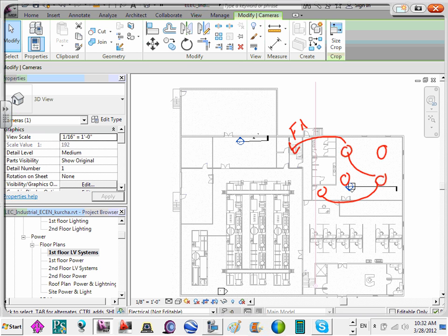that's going to your control panel. It's going to be circuit number 1. And then these two are going to go onto a separate circuit, circuit number 2. So what happens is, if one of these detectors goes off, it's not going to go into alarm. It may go into pre-alarm and give the building an indication that one of the smoke detectors went off. But the water and everything is not going to release until a second smoke detector on a separate zone goes off. So if both of these zones go off, it shuts down all the devices, releases the air in the system, lets the water go through, and puts everything out.